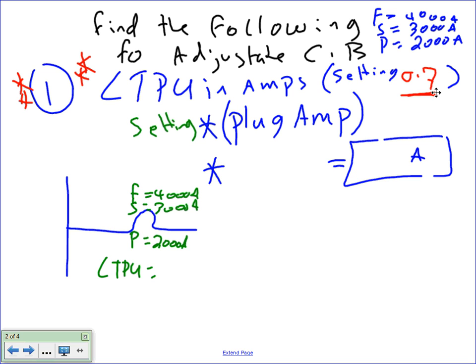Okay, I told you guys, you have this one. The same example that I told you, you should have it. So I'm asking about long time pickup in amps. The formula that you need to use is always the setting multiplied by the plug amps. What's the plug amps? What's the setting? I'm giving you a setting of 0.7, right? And what's my plug size? I'm giving you a plug of 2,000. Thank you, sir. 2,000. So if you take 0.7 multiplied by 2,000, what do you get? 1,400 amp. So this circuit breaker, for all practical sizing applications, is nothing but a 1,400 amp circuit breaker. Does that make sense? So you need to find the long time pickup setting.